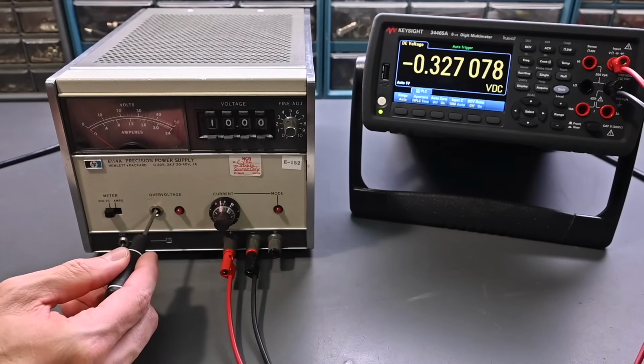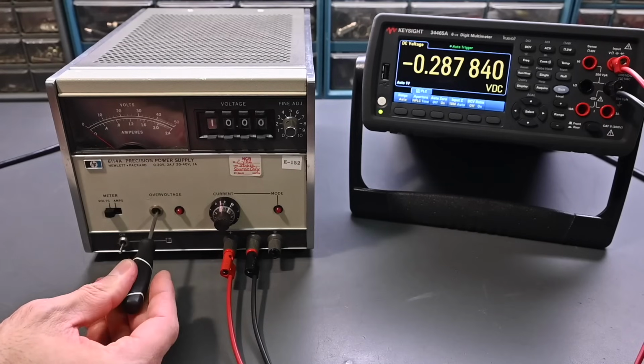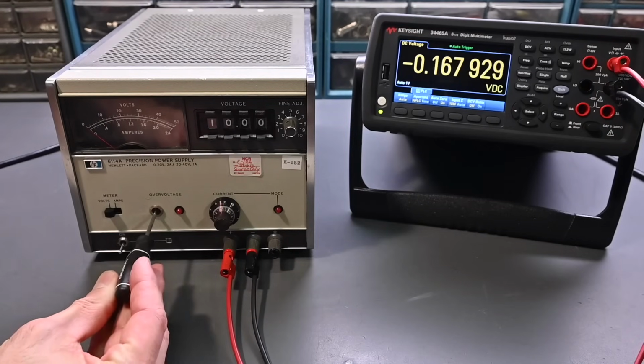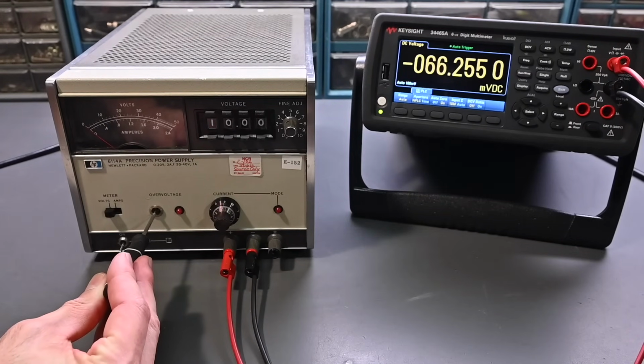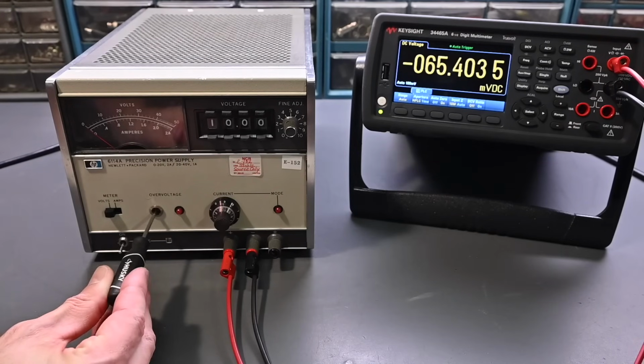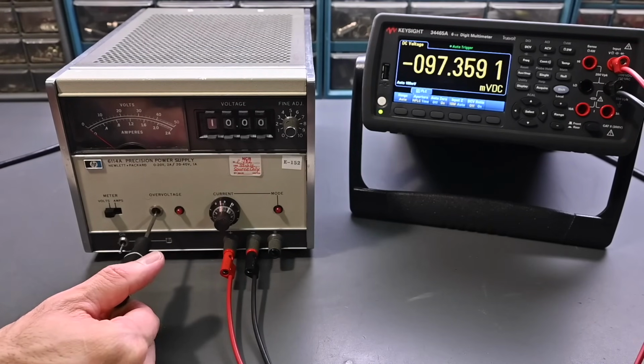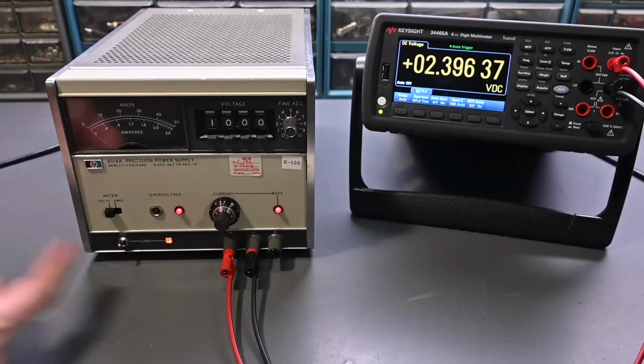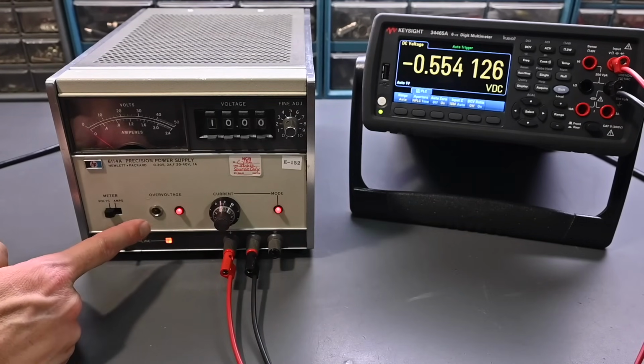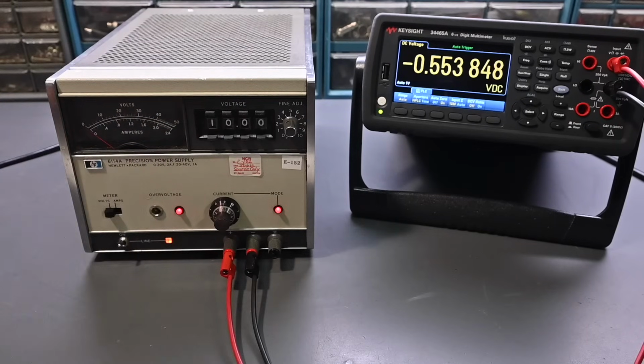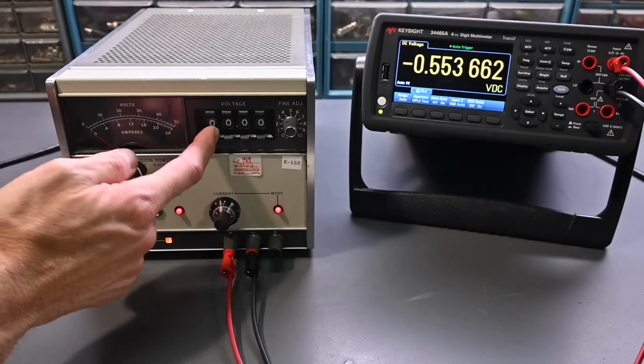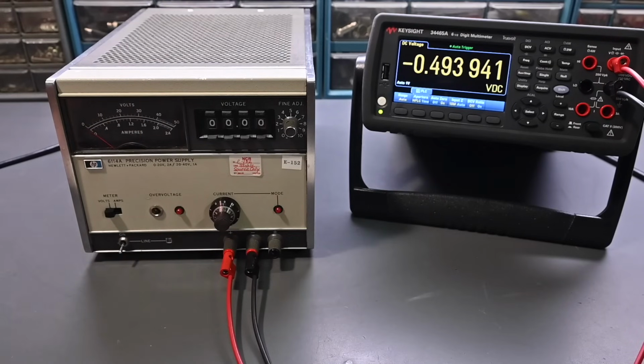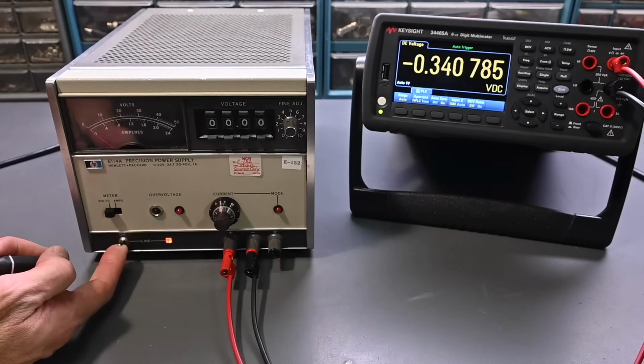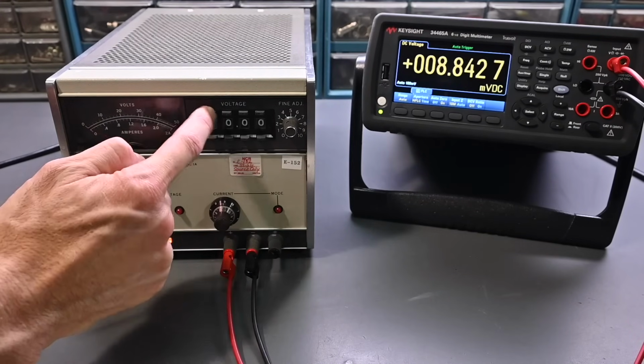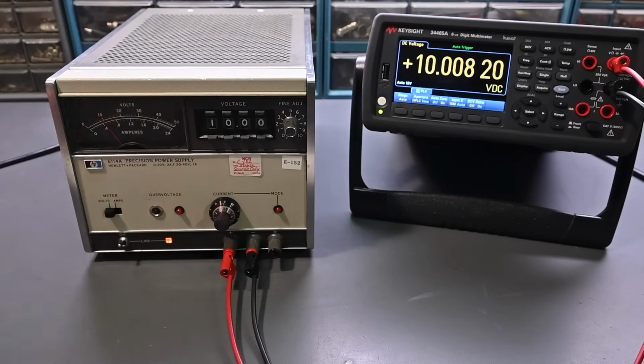Now, if I turn this, you can see I can rotate that all the way around, so there's minimum right there. That would be the lowest overvoltage setting. So I'm all the way back up. Okay, there it's at its maximum again. It went into overvoltage right away. So it's clearly a problem because overvoltage shouldn't be happening when that's at its maximum, and this is sitting right there at just 10 volts. That's not correct. So if I reset that, let's try again. See, 10 volts, now it's okay.